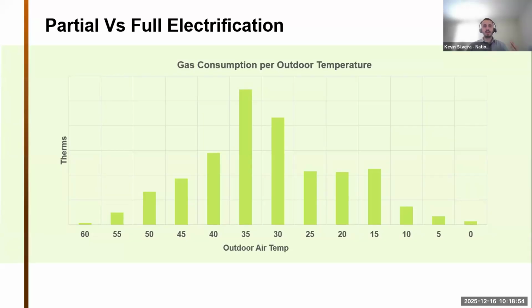So with that, I kind of want to take some time to look at full versus partial electrification. When we're looking at these buildings, the majority of your energy consumption happens above 30 degrees. So partially electrifying your building can go a long way to reducing your greenhouse gas emissions and doing it at a fraction of the price. As you get lower and lower temperatures, the efficiency of those heat pumps to move heat reduces, and therefore your electrical capacity needs to be increased in order to achieve that electrification.